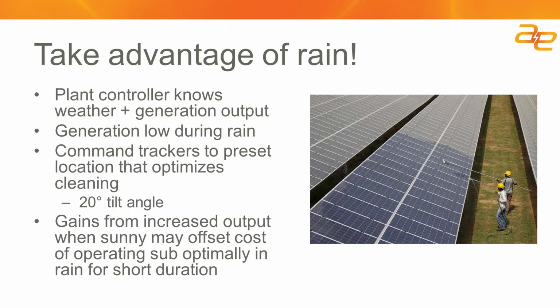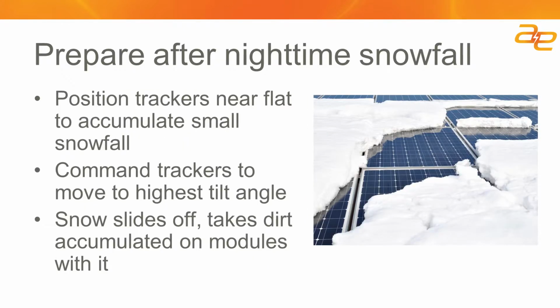So you may lose a little bit of energy if you're not pointed far to the west at the end of the day when there's a rain event, if you move the trackers closer to a flat position. But the energy lost might be easily recovered in a single day if you can reduce soiling by 5 or 6%. If you live in an area where snowfall comes, snowfall is actually the best way of cleaning soiling off a panel.